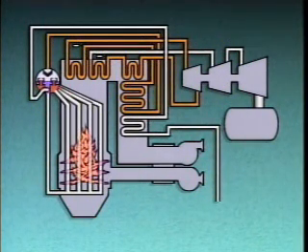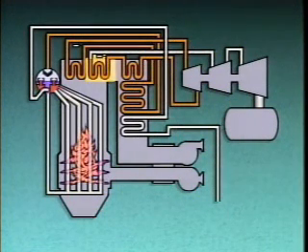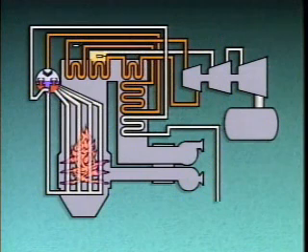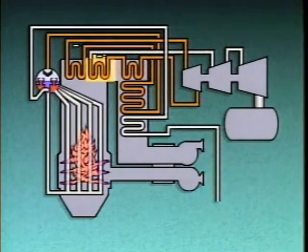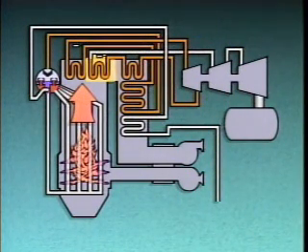After the steam flows through the primary reheater, it moves on to a secondary reheater. And a temperator, located at the beginning of the secondary reheater, is used to control the final temperature of the superheated steam leaving the secondary reheater. The temperator sprays water into the steam flow if the steam gets too hot. The secondary reheater in this example can also be classified as a radiant reheater because it's located in a line of sight with the boiler flames and receives most of its heat by radiation from the flames.